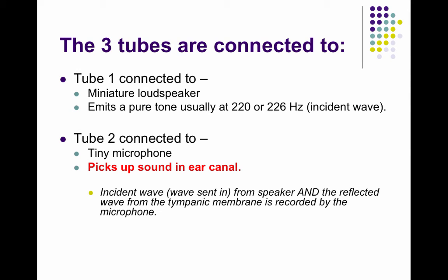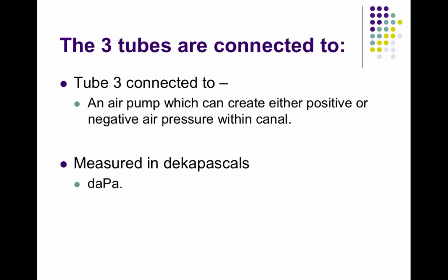The first tube is connected to a miniature loudspeaker that sends out a pure tone around 220 or 226 hertz. The second tube is a tiny microphone that picks up the sound reflected in the ear canal, and the third tube is an air pump that creates either positive or negative pressure.